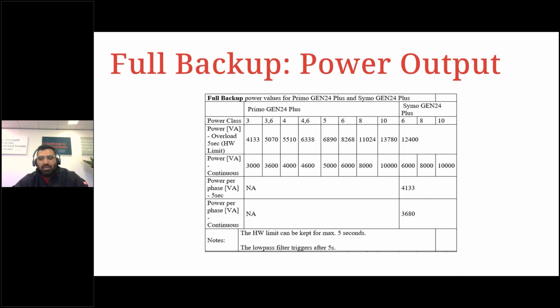As you can see from the table, the continuous output power in full backup is the same as the power class of the inverter. If you look at the continuous power of a SYMO 10 kilowatt inverter, it can do 10 kilowatt backup. Similarly, a 10 kilowatt single phase inverter can do 10 kilowatt continuous output power. In backup, the 3-phase inverters produce phase unbalance, and the max continuous power in a phase for a SYMO inverter is about 3,680 watts. So on SYMO inverters, if you go over 3,680 watts in one of the phases in a backup scenario, the inverter will go into an overload trip. This is something you will need to consider to avoid overload trips when setting up a full backup circuit.